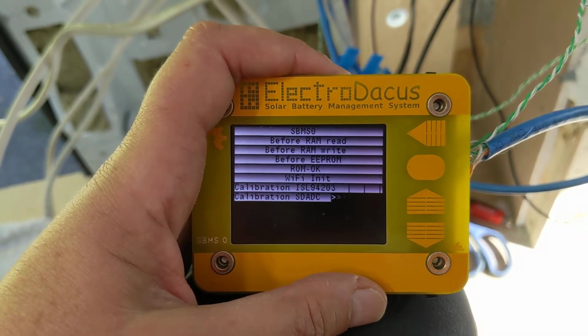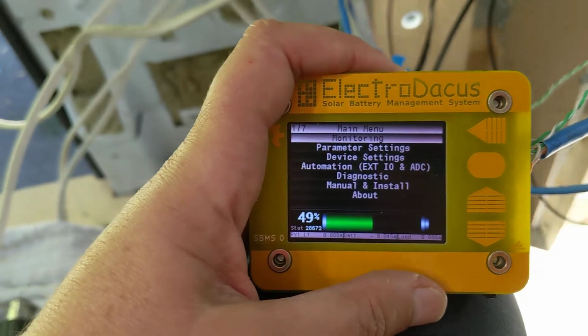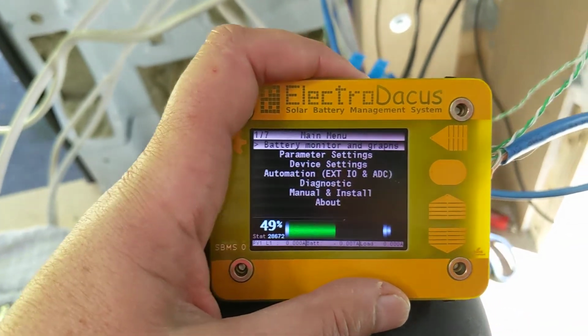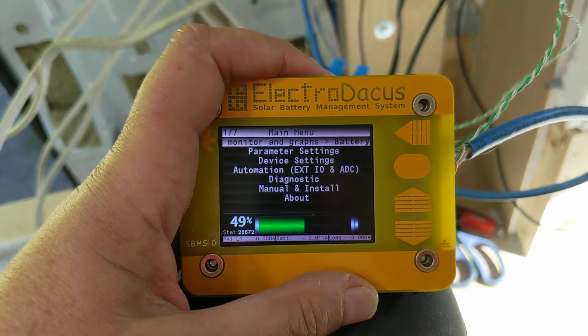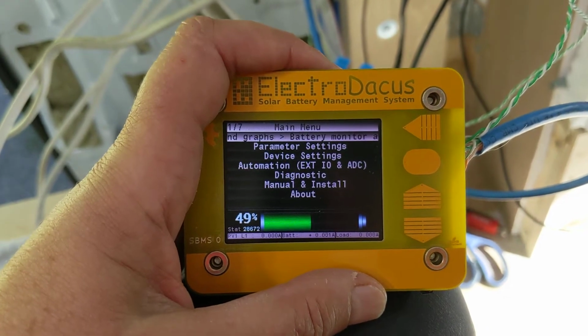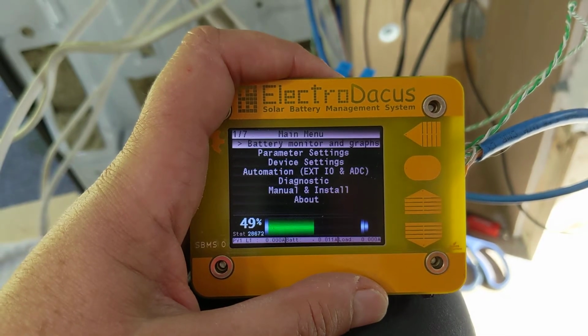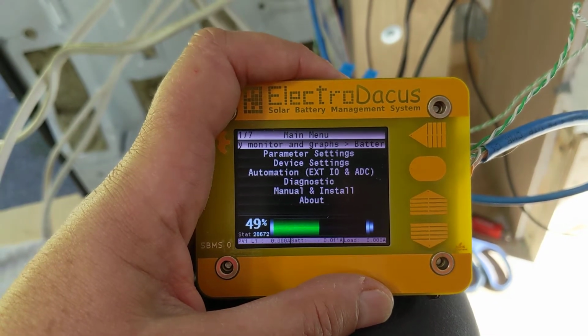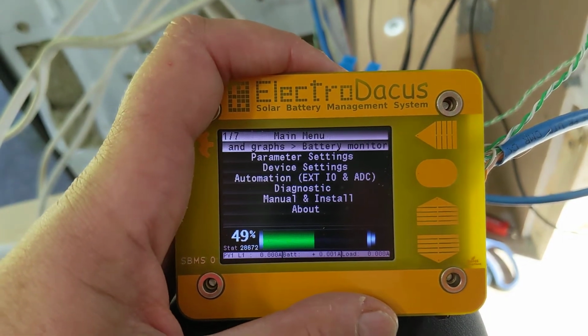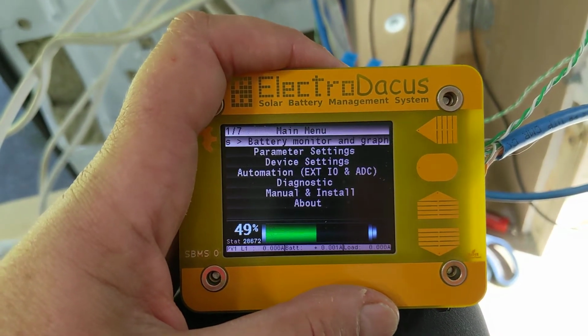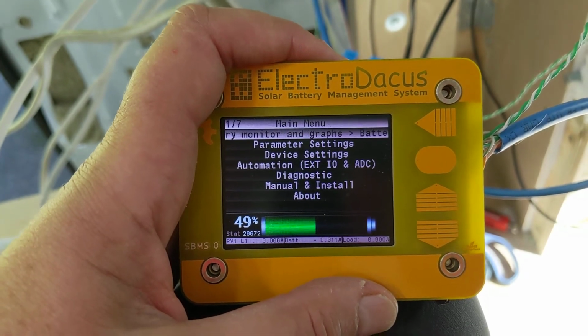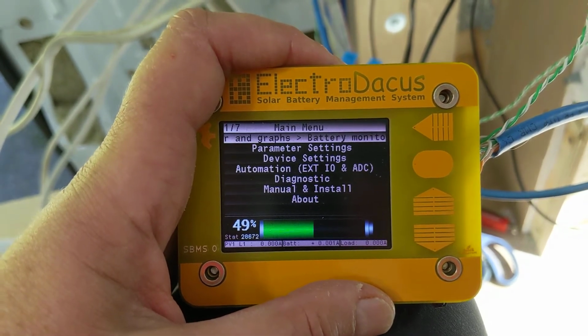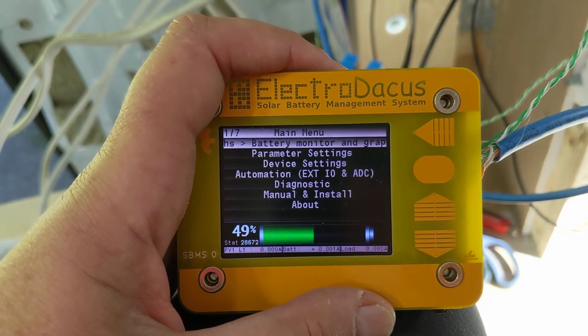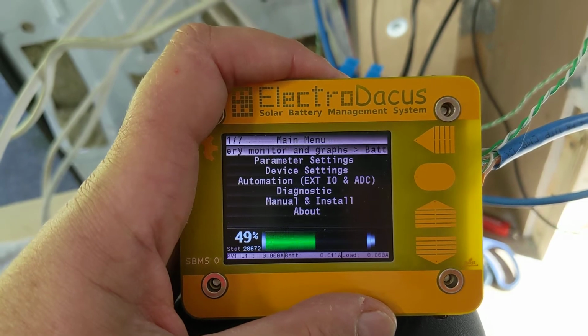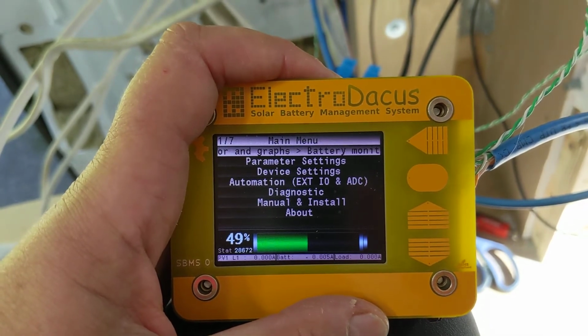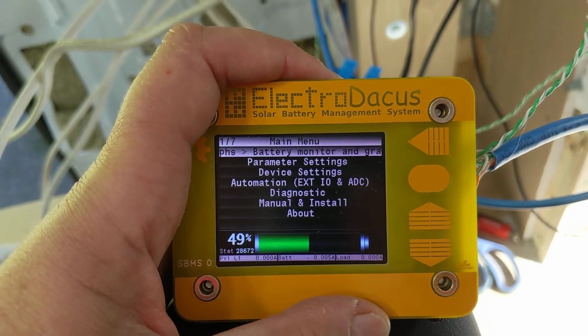You can see here it's calibrating the ADC shunt. The first thing that's a little bit mysterious is that even though there's no power flowing, the battery value is bouncing around between negative 11 milliamps to positive 1 or even sometimes positive 7 milliamps. This seems to be related to the current consumption of the BMS itself. For example, I found that turning on Wi-Fi will cause that number to more reliably go to a negative value, perhaps in the 20 milliamp range.